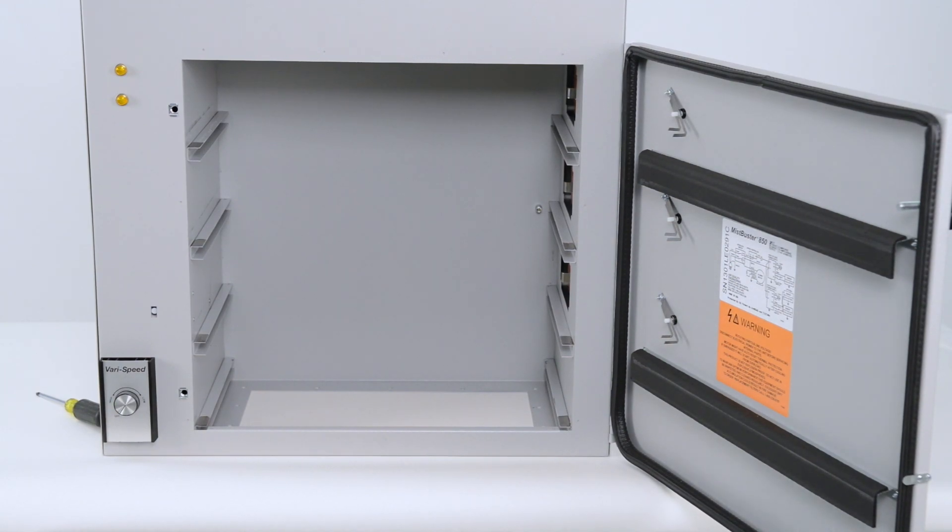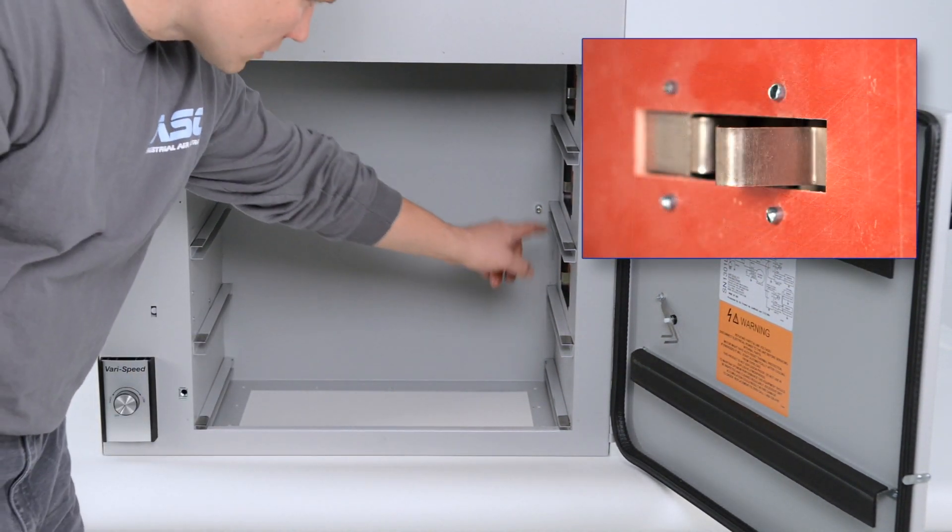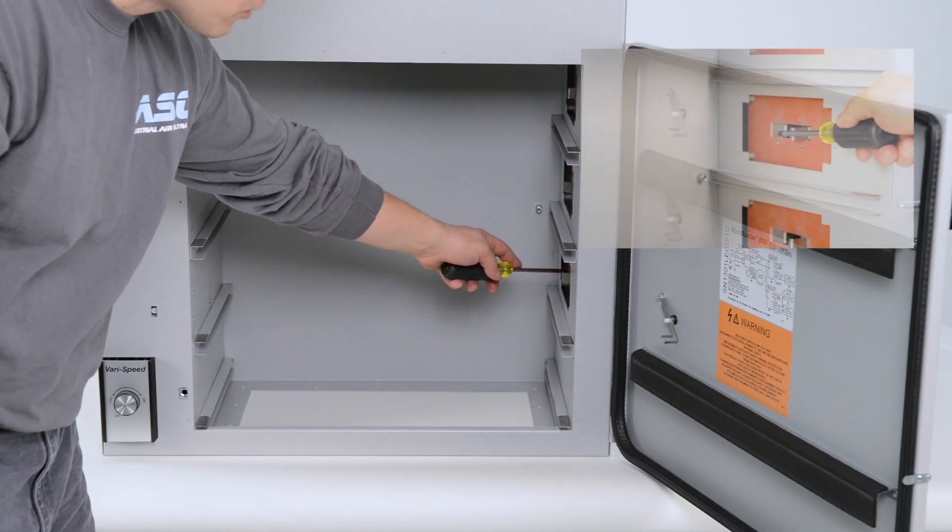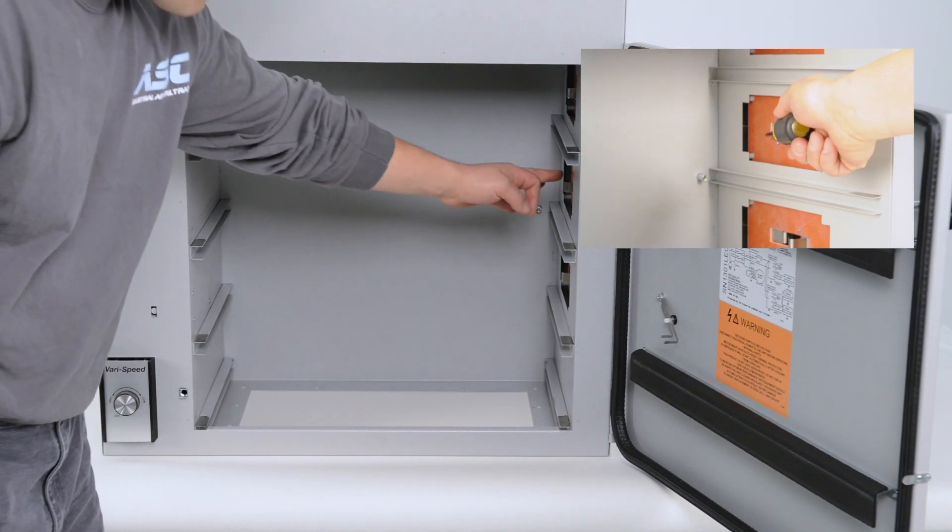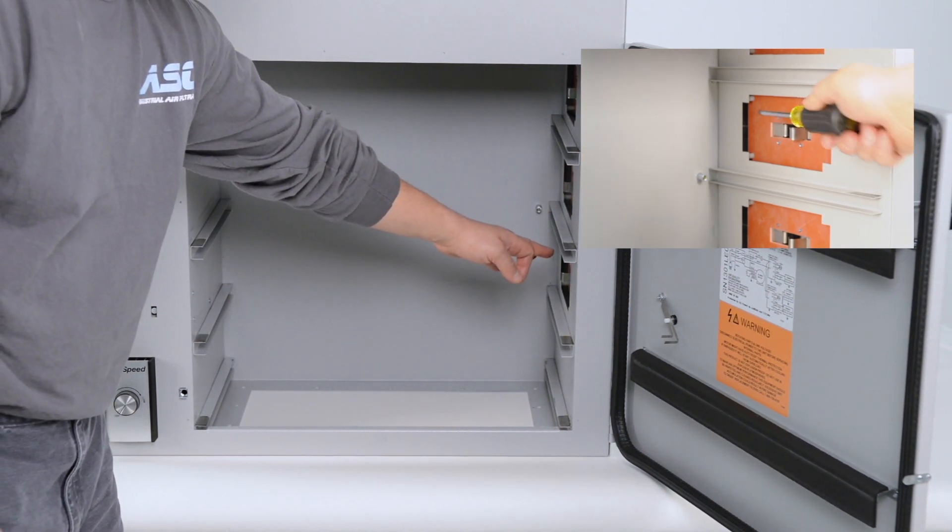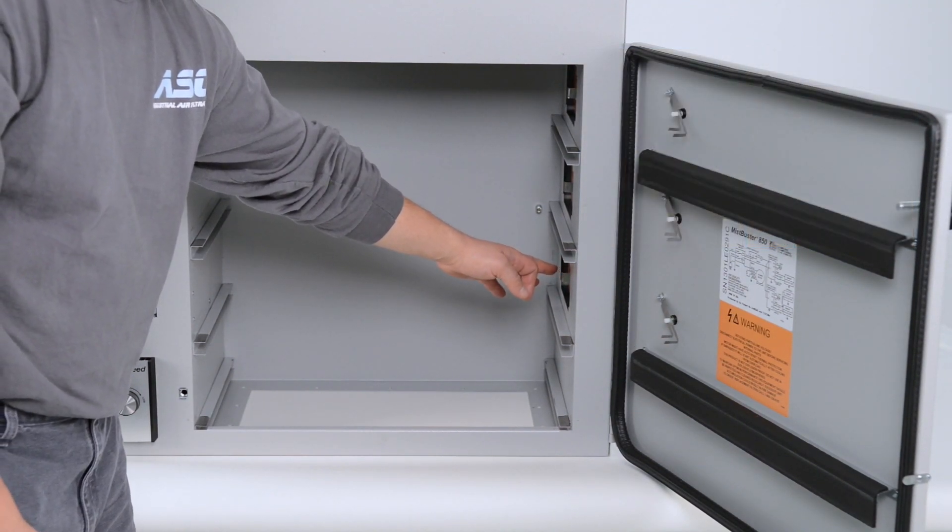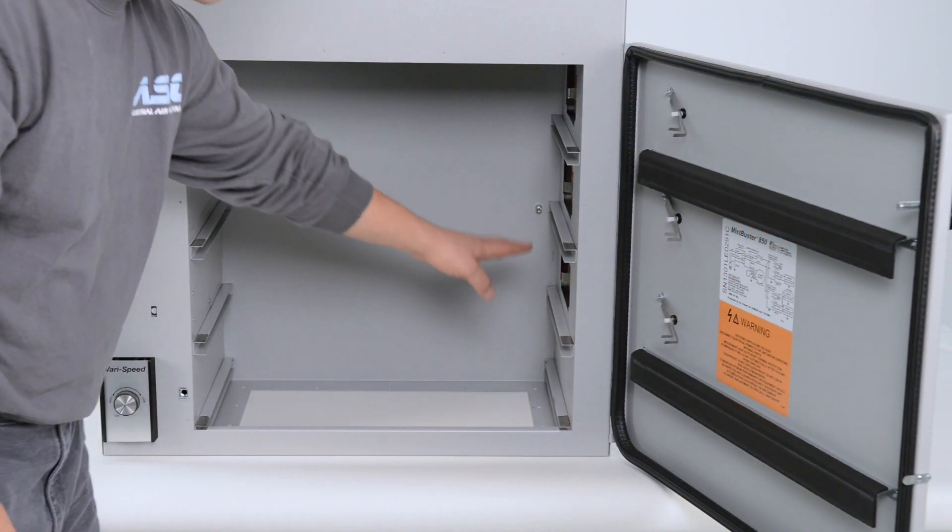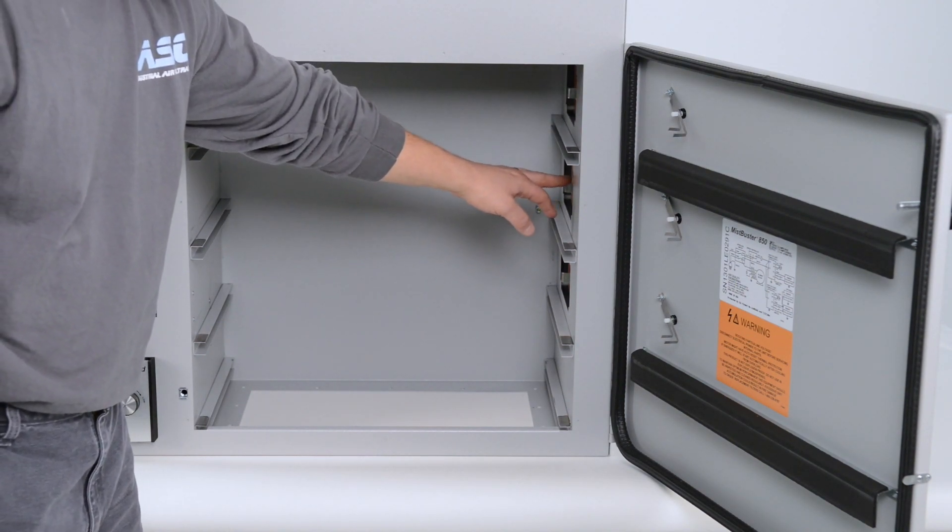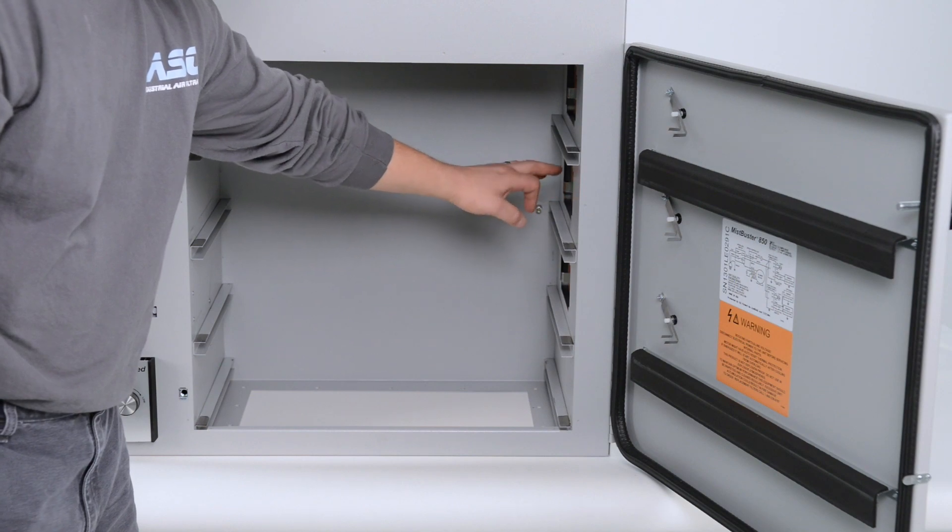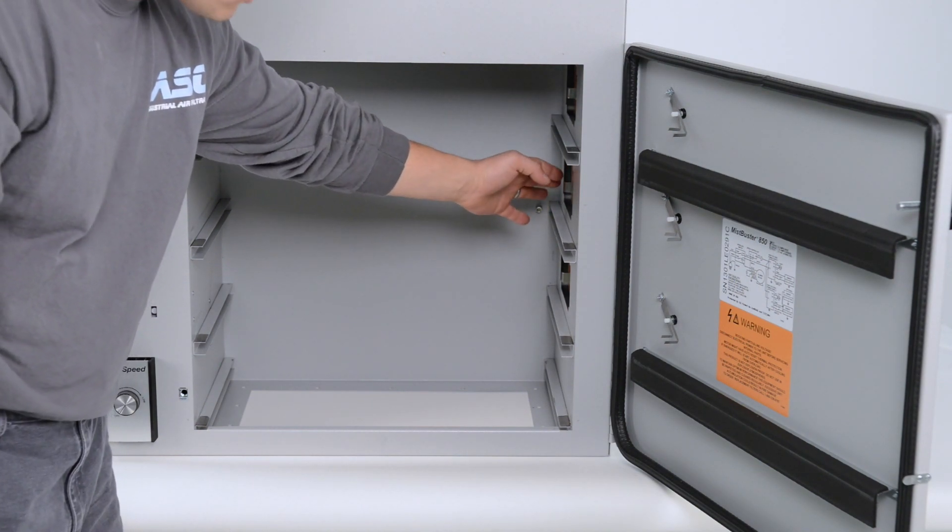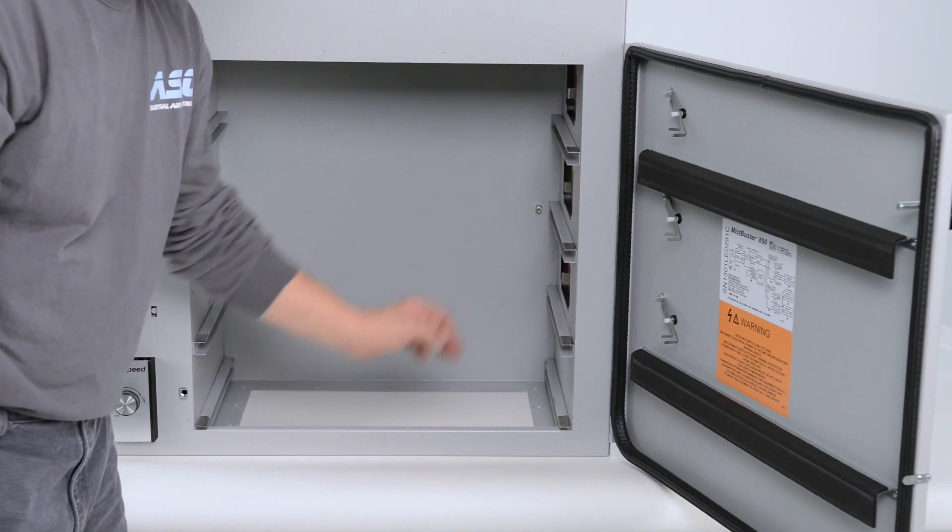You then want to check the connection points inside the unit, ensuring that they are clean and free of any grease or oil. You can use simple green or a scrub pad to clean off any excess grease. If you don't, you might have arcing which would cause the unit to malfunction. So you want to make sure that these contact points are clean and free of grease.